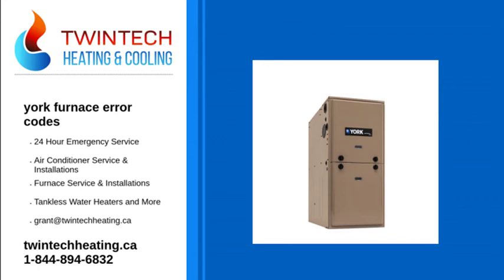Code: 8 red flashes. Result: this fault is indicated if the flame is lost 5 times (4 recycles) during the heating cycle. This could be caused by low gas pressure, dirty or faulty flame sensor, or faulty gas valve. The furnace will lock out for 1 hour and then restart.